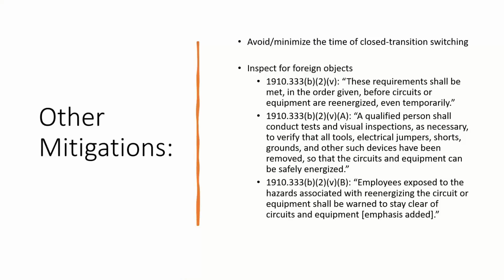Russ, I'm going to let you talk about this a little bit. Talk to us about closed transition switching and how to avoid and minimize that. Okay, and that comes down to mostly main bus situations, or maybe you have a substation that you can feed from two different sources. Whenever you close that tiebreaker and those two sources are tied together, your equipment may or may not be rated for the amount of fault current that's available there. There was a time not too long ago when that was standard engineering practice when you designed a substation. You'd say, anytime that tie is going to be closed and the two systems are tied together, we know those breakers are underrated, but it's going to be for such a short amount of time that it's okay.